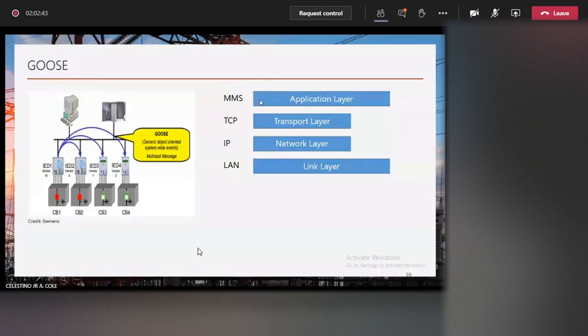Now there are cases where there's a lag here, where the message is delayed in giving a multicast in case of an event. So the GOOSE message has the capability to bypass this TCP/IP. Meaning, from the master, when there's a substation event, a very emergency situation, it bypasses the TCP/IP and goes directly to the link layer.